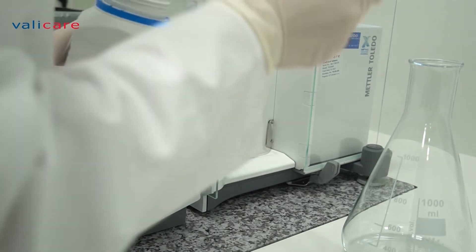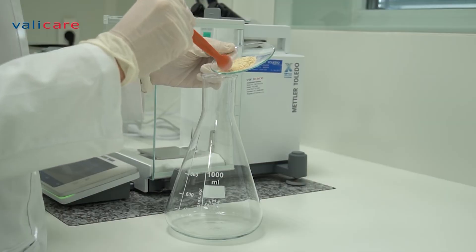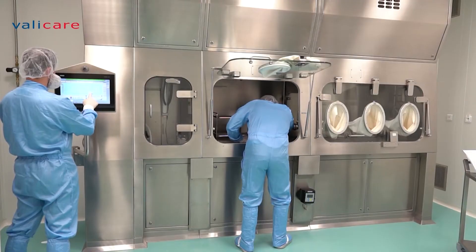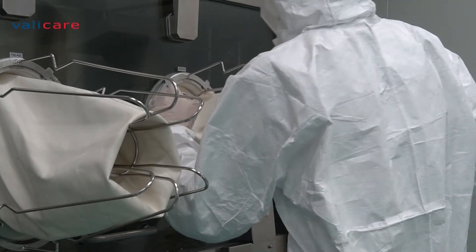The building itself comprises a microbiological section and a clean room with an isolator, maintaining ISO grade 5 conditions. Our focus is the validation of biodecontamination of isolators and clean room installations by means of vaporized hydrogen peroxide.